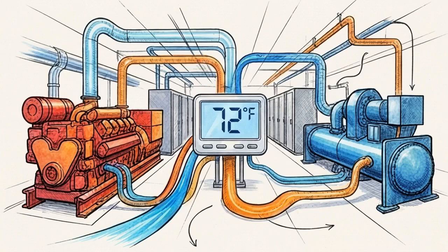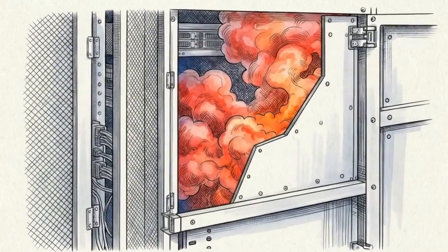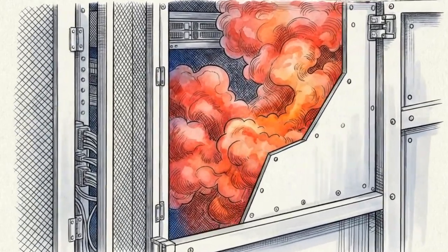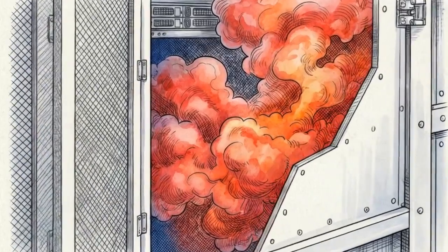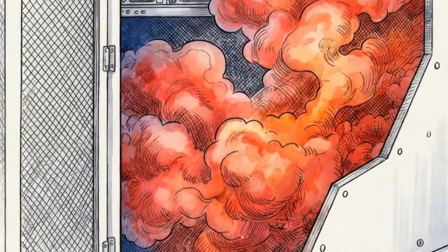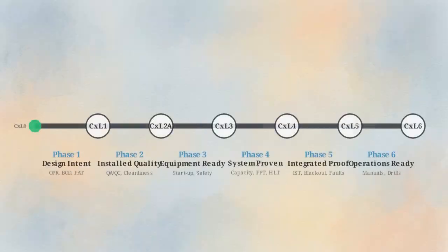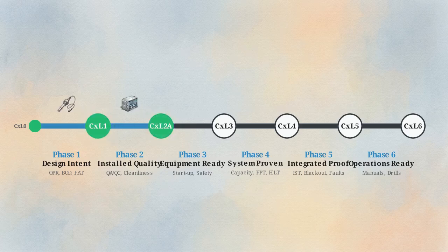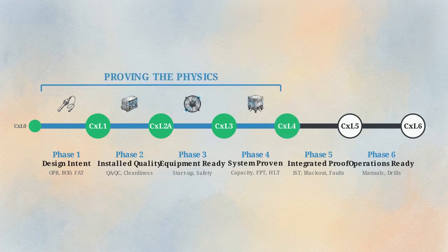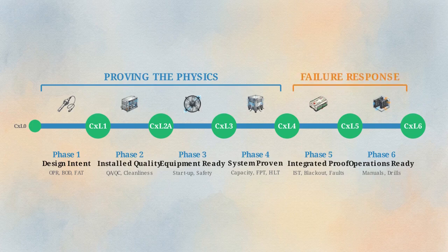A stable 72-degree reading on a data center floor is often an illusion. Without full visibility into the thermal path, that steady temperature might hide a mechanical system running on the absolute brink of failure. Mechanical commissioning removes this ambiguity. It operates as a rigid, chronological risk retirement framework, requiring us to prove the underlying physics before we evaluate how a system responds to a failure.